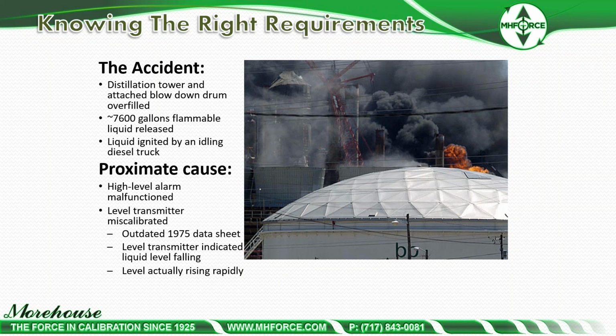Well, we have a distillation tower and attached blowdown drum. The drum overfilled, 7,600 gallons of flammable liquids were released, and it was ignited by an idling diesel truck. The high-level alarm malfunctioned. The level transmitter was miscalibrated, with an outdated 1975 data sheet. The level transmitter indicated liquid level falling when it was actually rising. Although a high tower alarm did activate in the control room in the early morning hours, the second high-level alarm malfunctioned. So people just didn't know what to do. It was a huge ordeal, a huge problem when you have this.